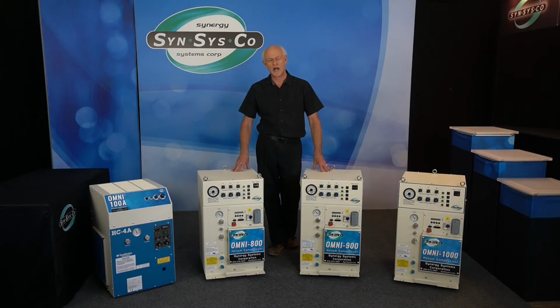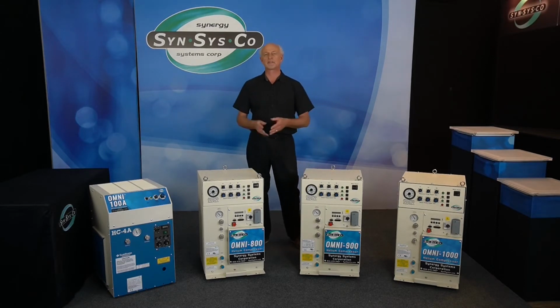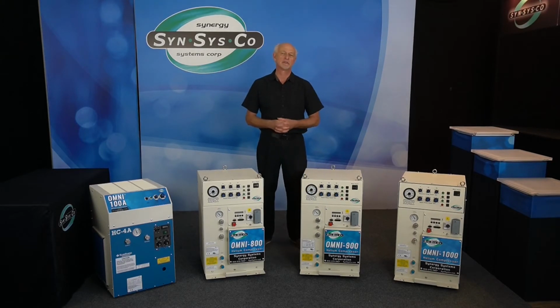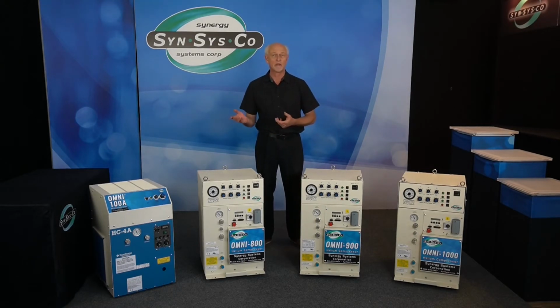When we became a distributor, we brought their Marathon line of equipment to the marketplace and quickly discovered gaps in the support of the existing installed base of compressors and cryopumps in the industry. The biggest gap was that many legacy compressors and cryopumps were not easily upgraded, because the OEMs had new systems that were not backwards compatible with the existing installed base. So if an end user wanted to upgrade a compressor or cryopump, they could not do it on an incremental basis. They would have to remove all the equipment and install the latest generation equipment because it was not backwards compatible.